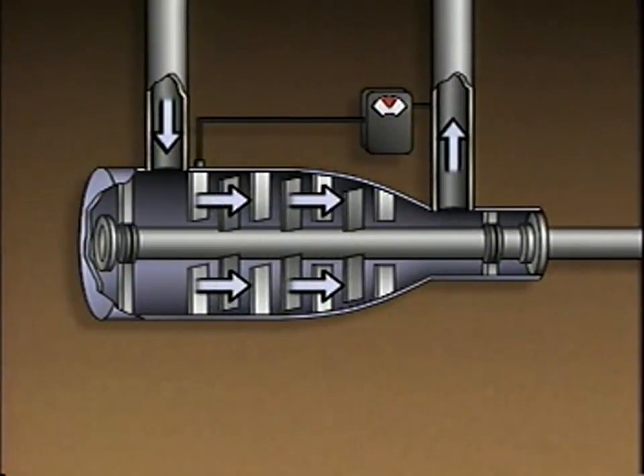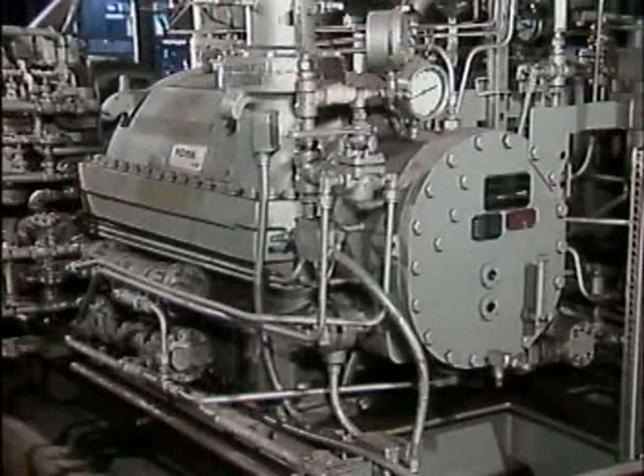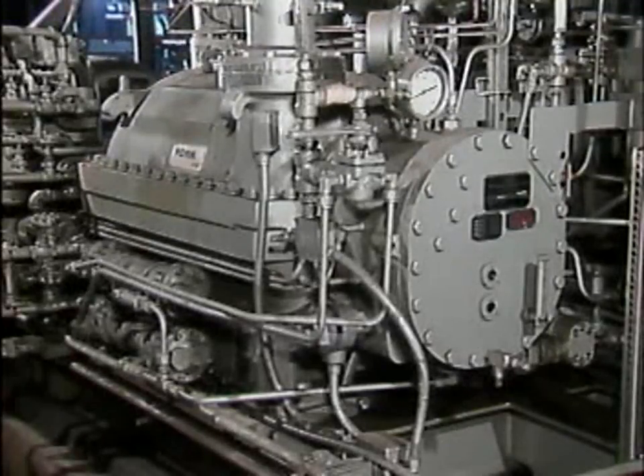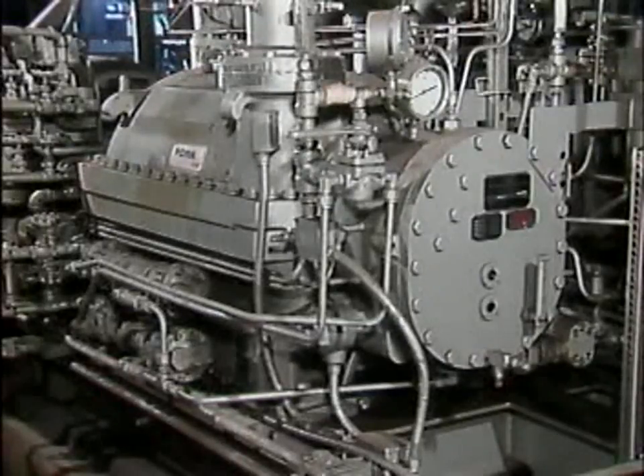So, by adjusting the flow of gas into the compressor, the control system maintains the discharge pressure of the compressor at the desired value. For a given discharge pressure, a compressor has a certain minimum flow rate. Below this flow rate, the compressor becomes unstable.